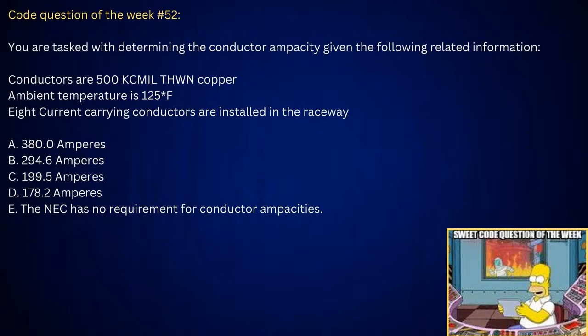You got 500 kcmil, and okay, you're using THW. Let me tell people what you need to do here when you look at this. He is throwing a curveball here. This is THWN, so you need to go look at Table 310.4(1), and when you pick up THWN and come across, it's going to tell you in the third column for its maximum operating temperature, it says 75 degrees. Now, if he'd put THWN-2, I could have used the 90 degree C column. But in this case, I have to use the 75 degree C column.